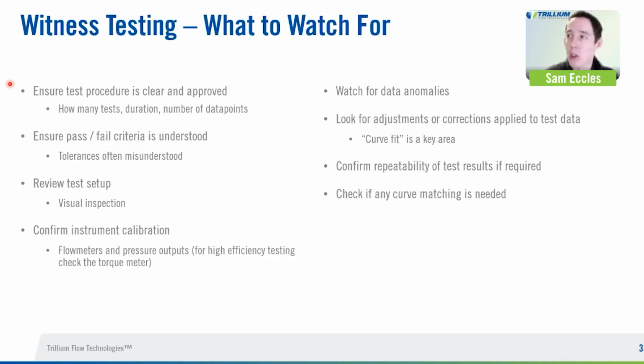So it's very important, especially if you're using a third-party inspector, that they are exceptionally clear on the test procedure that's agreed. So it's not going to be like the last test they saw. It's going to be how many tests, what's been agreed, what data points have been signed up for, and above all else, what's the pass and fail criteria. Because as we've talked about, you can have a huge miss on test and it still be completely acceptable within the tolerance. And that feels very uneasy to everyone involved, but it's something that people need to understand going in, solves so much confusion and back and forth after the event.